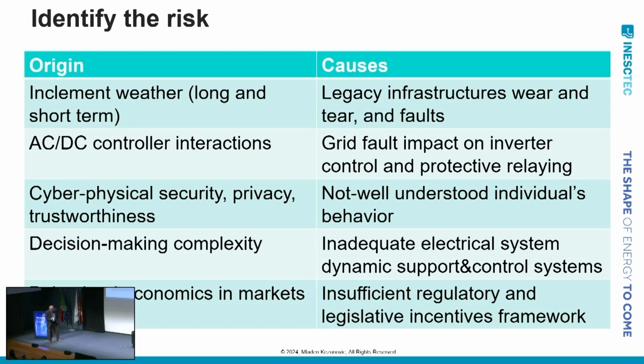So I've put a few up there. Weather is impacting the grid, both long-term and short-term. Long-term, the equipment deteriorates over time. I don't know what you have in Portugal, but we have in the United States, in some major cities, equipment that is 80, 90 years old still in service. Then we have short-term impact associated with sudden storms, wind, hail, whatever it is. One has to think about these two things being tied together, because if the equipment deteriorates, the insulation levels deteriorate. So if lightning strikes, the equipment is going to fail more likely than if it was new. In general, that is the case.